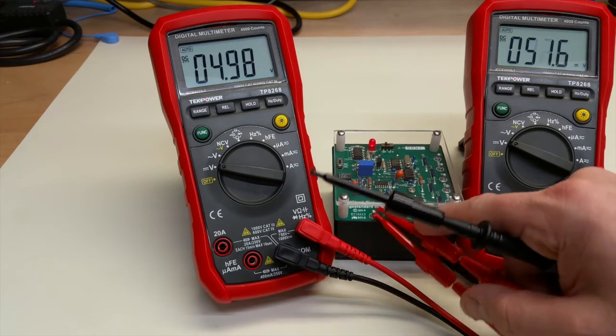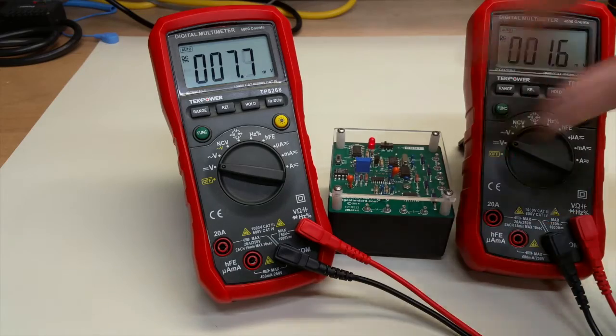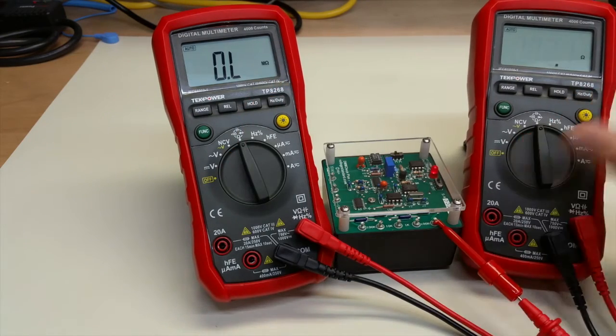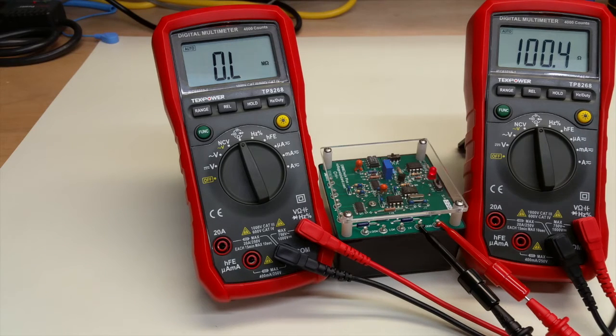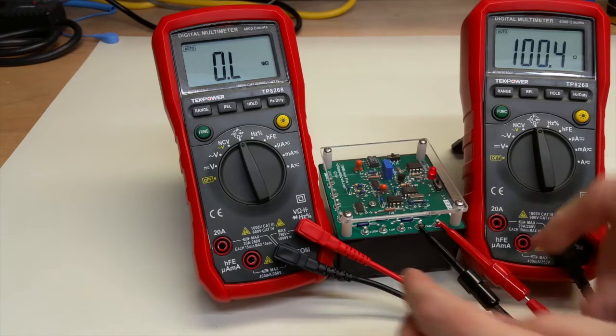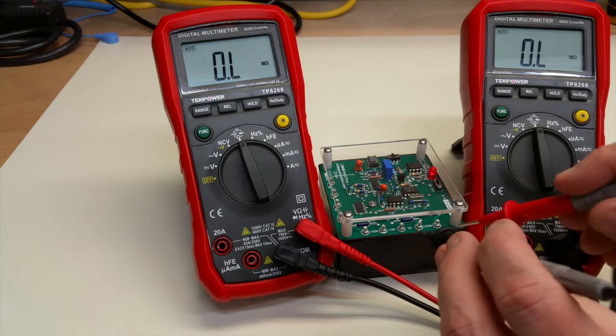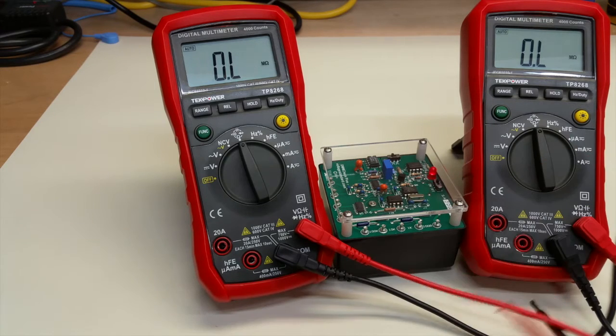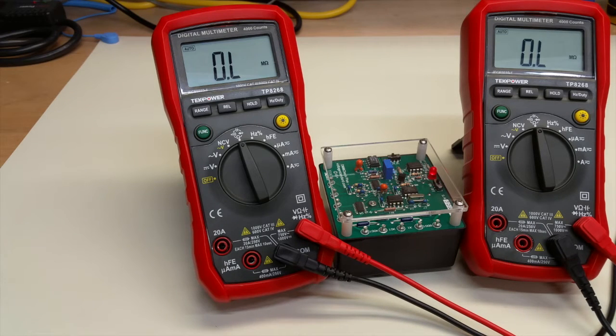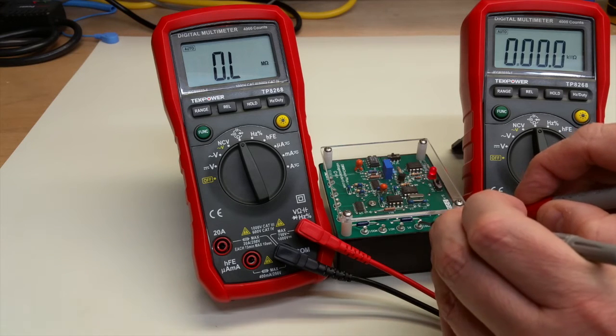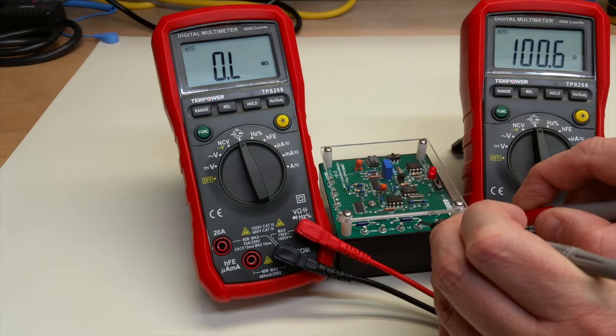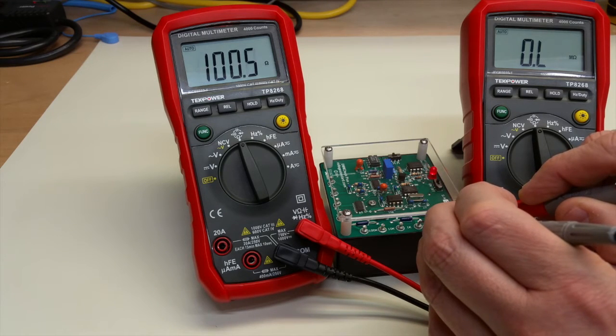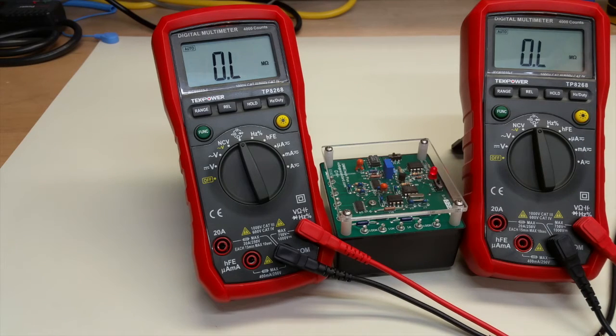So let's look at resistance next here. We're just going to now look at this and there are many different resistors we can look at. So for the 100 ohm resistor we're reading 100.4 ohms here and we're just going to take this off and look at the other meter now as well and we see that we get 100.5, certainly very good agreement between both the meters. I'm just going to get rid of these clips now and go back to the first one and we get 100.5, 100.6 and with the other meter we get 100.5 as well. So they're certainly consistent, they're also within spec.